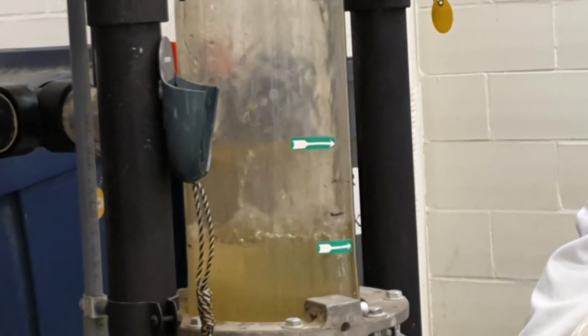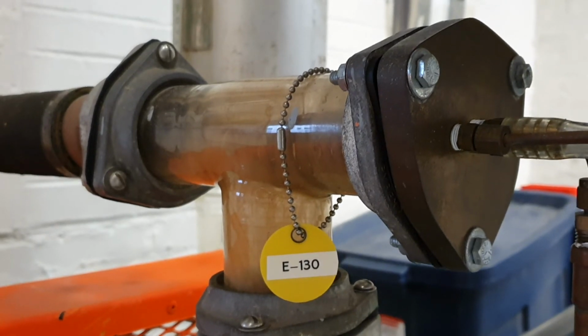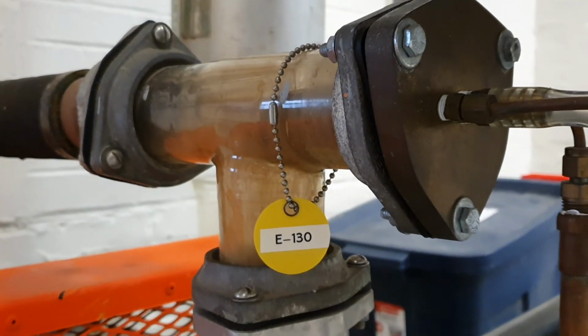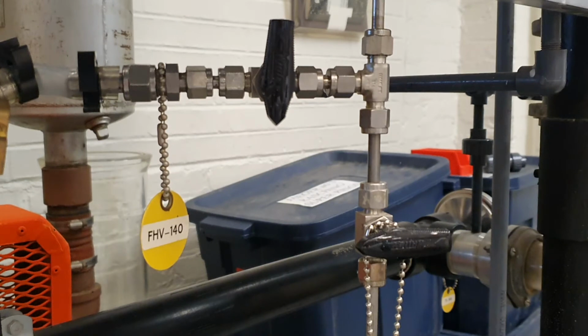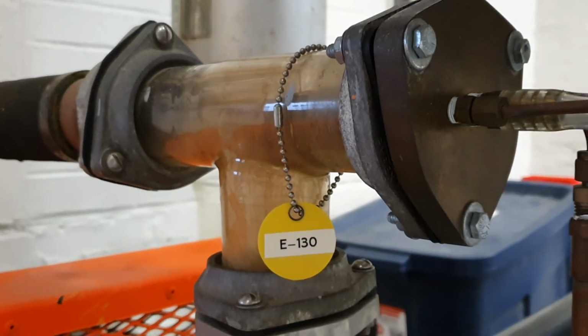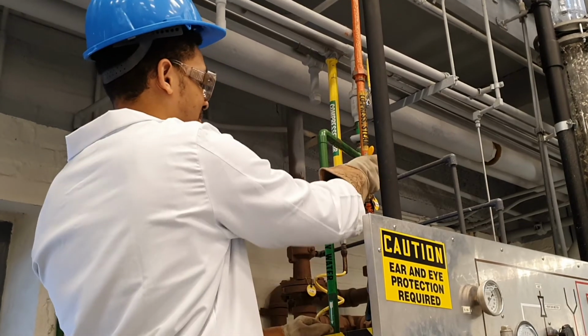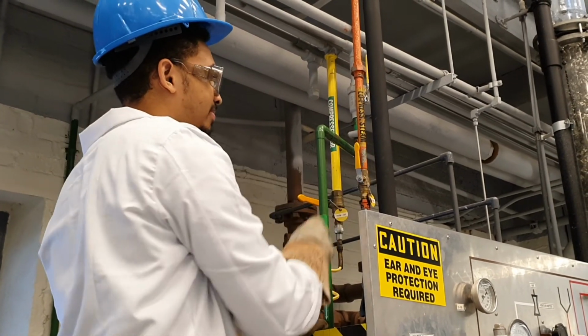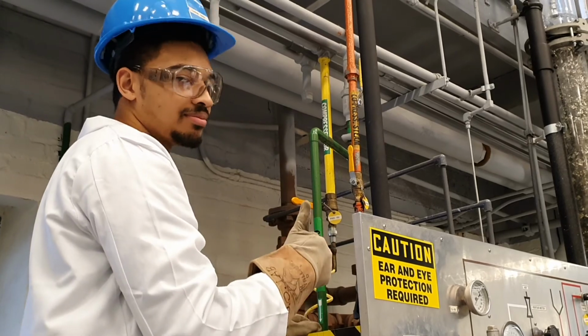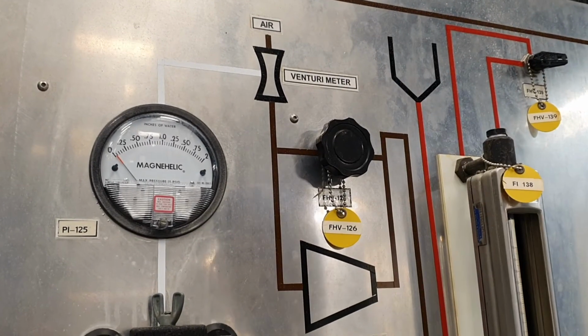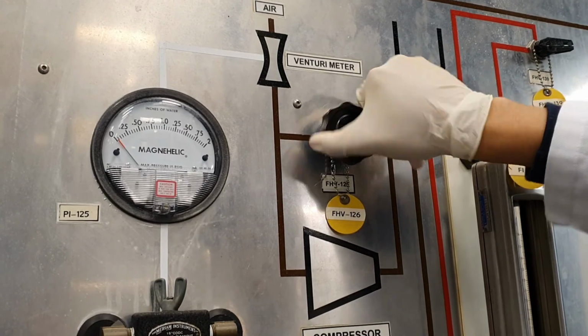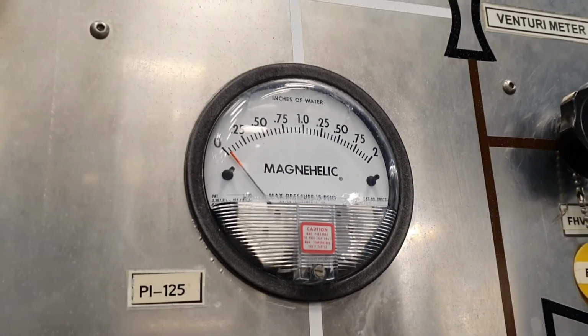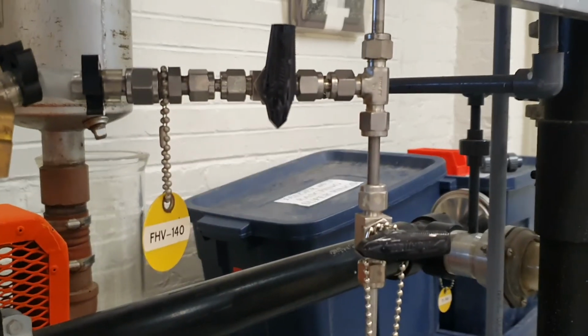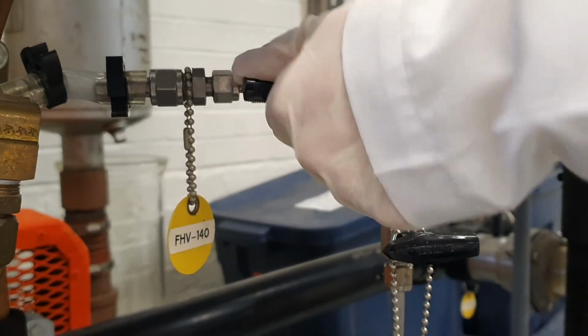Another hazard to be aware of is if liquid acetone begins entering heat exchanger E130. If this occurs, close valve FHV 140 to ensure that no more liquid acetone is entering E130. Then, make sure steam is entering the system by ensuring valve FHV 116 is open. Also check that the air flow rate entering the system is set to the desired value. Once both the air flow rate and steam valves are checked, FHV 140 can be reopened to allow acetone to enter the system again. Finally, in case of an emergency, follow the shutdown procedure.